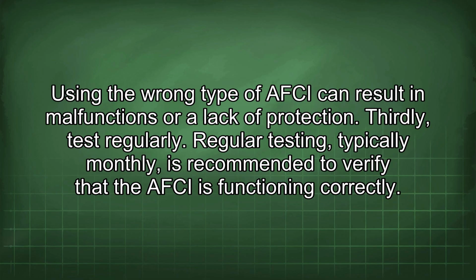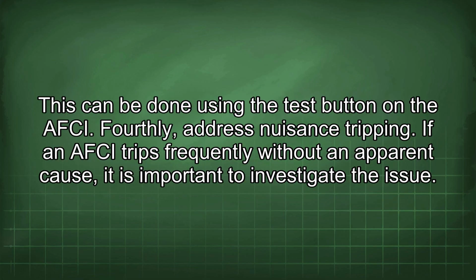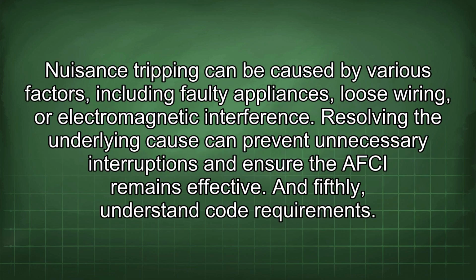Thirdly, test regularly. Regular testing, typically monthly, is recommended to verify that the AFCI is functioning correctly. This can be done using the test button on the AFCI. Fourthly, address nuisance tripping. If an AFCI trips frequently without an apparent cause, it is important to investigate the issue. Nuisance tripping can be caused by various factors, including faulty appliances, loose wiring, or electromagnetic interference. Resolving the underlying cause can prevent unnecessary interruptions and ensure the AFCI remains effective.